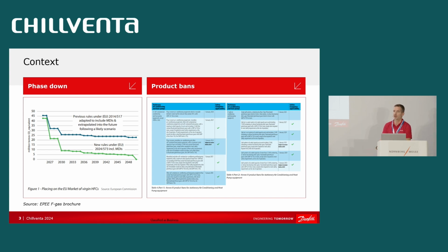Of course, there still are A2L alternatives of low GWP like R-455A, R-454C. But you all know those are blends with a high HFO content. Who knows what will happen with the REACH regulation in a few years from now. So basically, the precautionary principle dictates to use propane whenever, wherever it can be used. Simply, it's the great refrigerant, with the best thermodynamic properties, except for the high flammability.